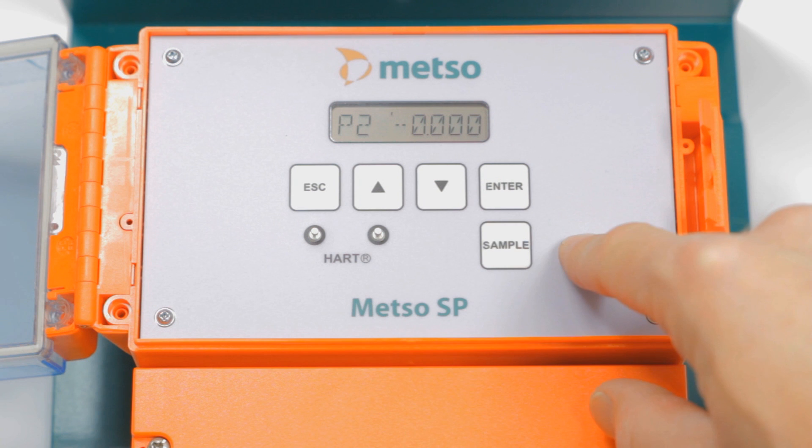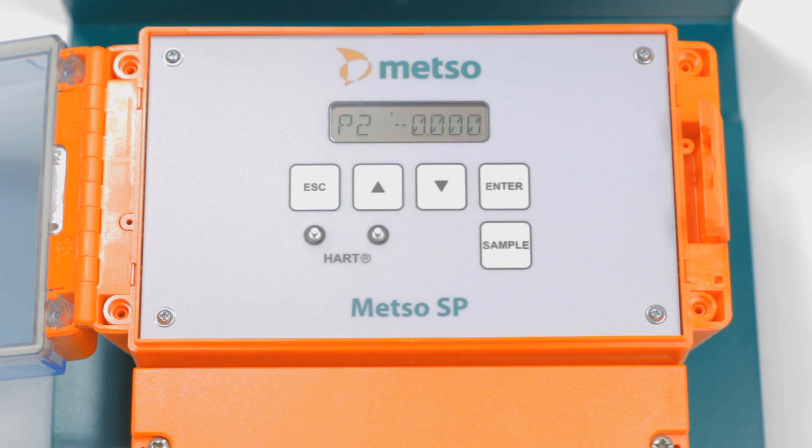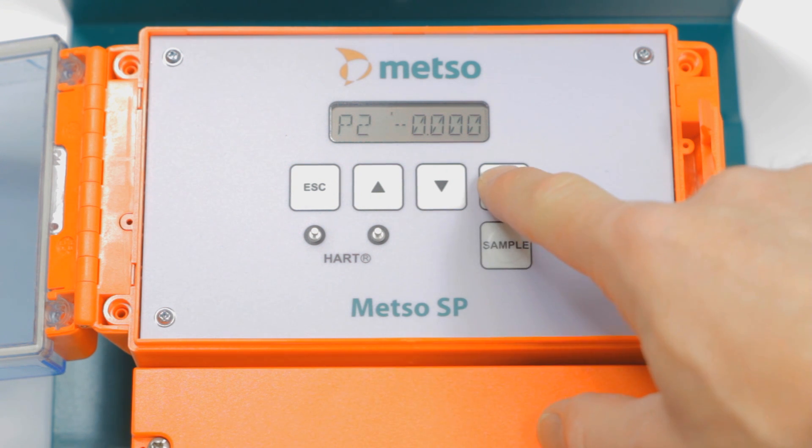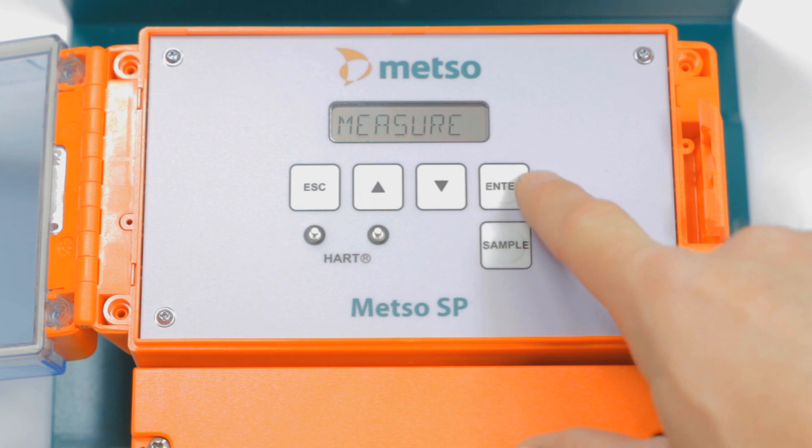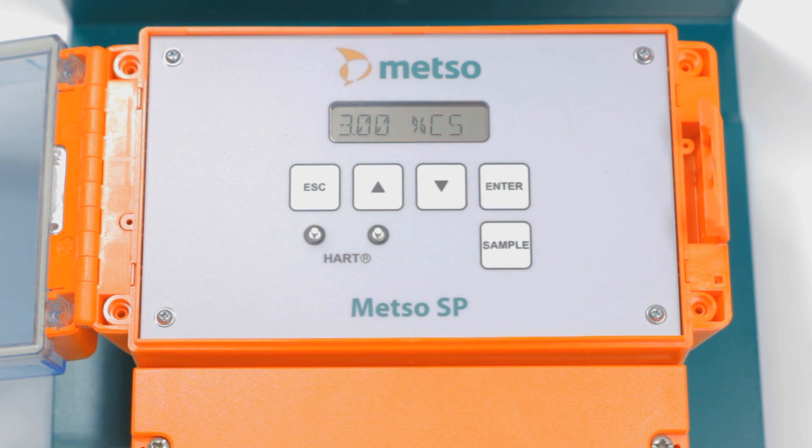So what we're going to do is increase the SmartPulp reading by 0.06. We're going to arrow up. We're going to make sure it reads 0.06. Hit enter, save, okay. And we go back to our measure, and we're reading 3.00%.